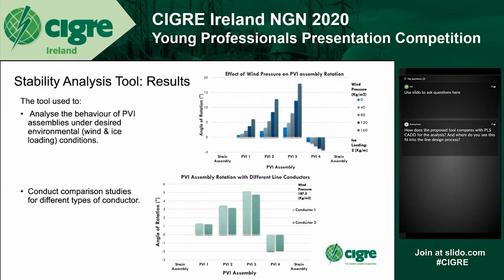As can be seen from the graph, conductor 2, which was a slightly larger and heavier conductor compared to conductor 1, produced lower deflection for the PVI assembly for the same weather conditions or operating conditions. This was a very meaningful insight into the conductor selection process.